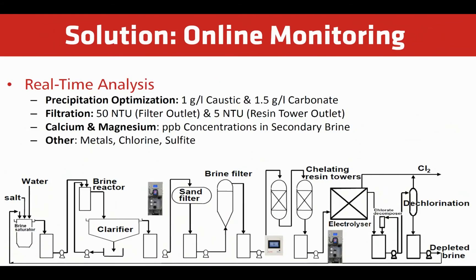Galvanic recommends using online analyzers that can handle difficult brine conditions. Caustic and carbonate can be monitored in the primary purification stage to optimize hardness removal. Turbidity or suspended solids can be monitored at the filter and resin tower outlets to optimize filtration. Total hardness can be monitored in the secondary brine before electrolysis to protect the membrane cell.